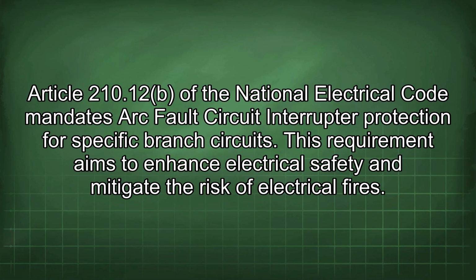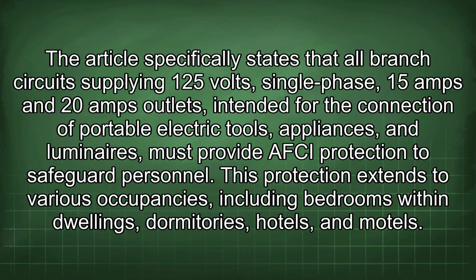Article 210.12 of the National Electrical Code mandates arc fault circuit interrupter protection for specific branch circuits. This requirement aims to enhance electrical safety and mitigate the risk of electrical fires. The article specifically states that all branch circuits supplying 125 volts, single-phase, 15 amps and 20 amps outlets intended for the connection of portable electric tools, appliances, and luminaires must provide AFCI protection to safeguard personnel.